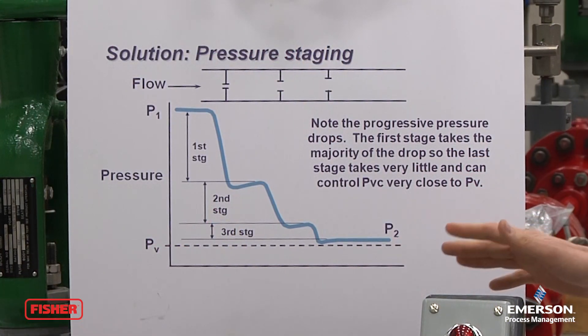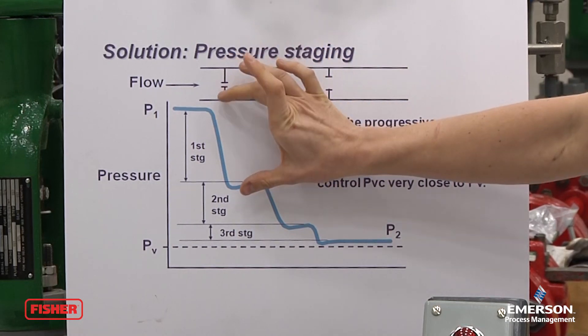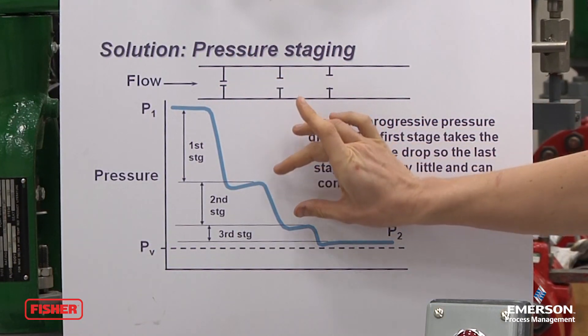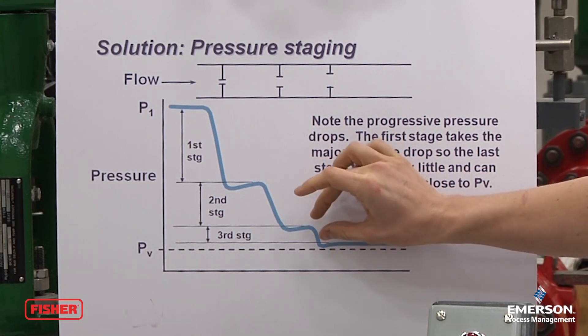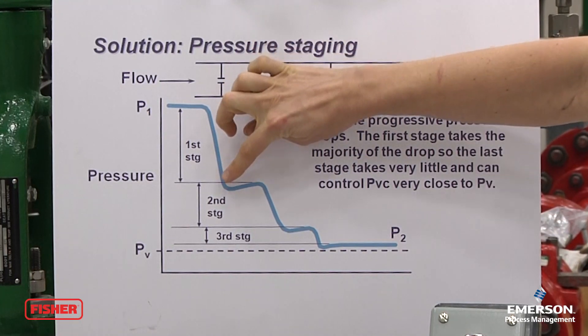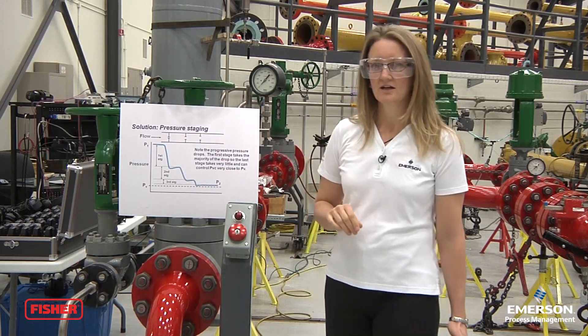For example, with our Cavitrol II and III stage products, we can take a large pressure drop across the first stage and then take another pressure drop across the second stage, or if we need it, we can even add a third stage. By doing this, we can ensure that each vena contracta stays above the vapor pressure, and by doing that, we eliminate all cavitation.